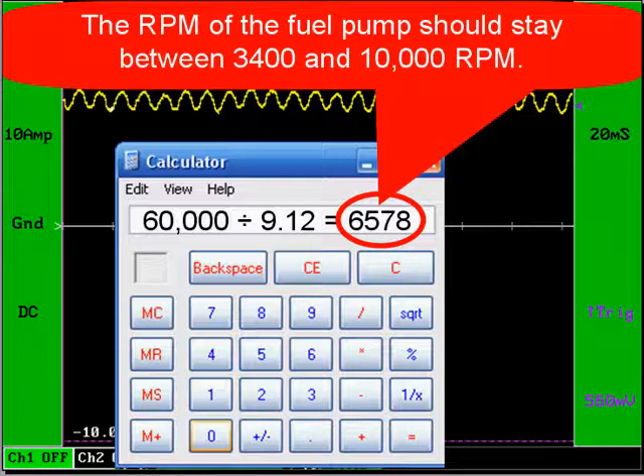Here's how you determine the pump's RPM. You take the number 60,000. We get that number from the 60,000 milliseconds in 1 minute. You divide it by the time your pump takes for 1 revolution. Our example was 9.12. That equals 6,578 RPM. Our pump is within specs.